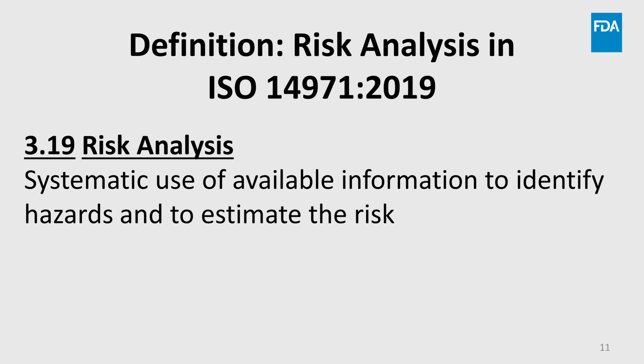According to ISO 14971 3.19, risk analysis is a systematic use of available information to identify hazards and to estimate the risk. Please be aware there are many risk analysis techniques available, and like any tool, their use depends on what you intend to get from it. I will note a few of the more common techniques later in this module.